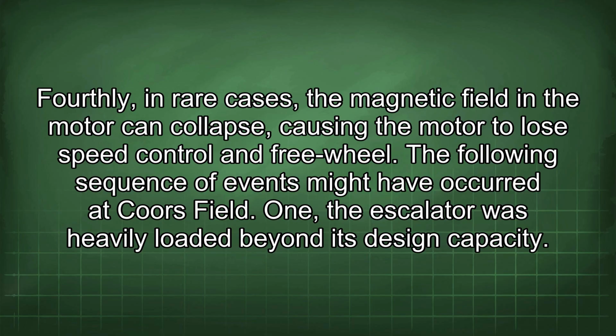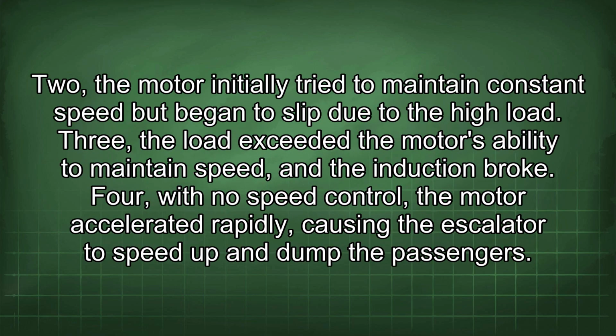Fourthly, in rare cases, the magnetic field in the motor can collapse, causing the motor to lose speed control and freewheel. The following sequence of events might have occurred at Coors Field. 1. The escalator was heavily loaded beyond its design capacity. 2. The motor initially tried to maintain constant speed but began to slip due to a high load. 3. The load exceeded the motor's ability to maintain speed, and the induction motor broke down.